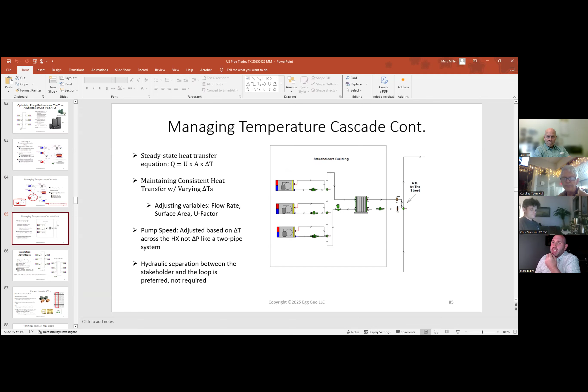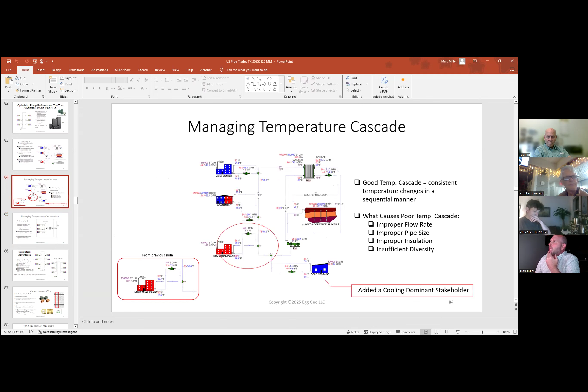So to answer your question about the glycol, there could possibly be propylene glycol in this ambient temperature loop. Propylene glycol, though, is food grade safe. And now they actually make one that's 100% biodegradable that can have incidental food contact. It's made by Corchem. So this glycol can contact food and you can consume the food and be safe. But the use of glycol is dependent upon the conditions and the design of the system, if you're going to be reaching near freezing temperatures in this ambient temperature loop. In this particular design, where we're reaching 36 degrees, it may be conceivable that the loop may require glycol to prevent freezing. Without glycol, this becomes a typical closed loop system where you have to add inhibitors, just like any other closed loop hydronic system in a building.